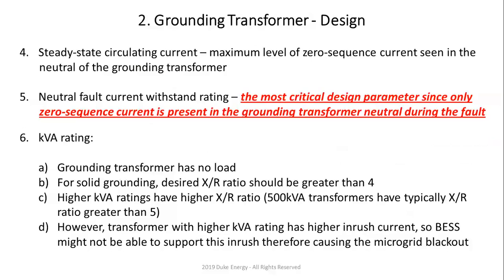So the maximum level of zero sequence current is pretty much the current flowing between the wye ground and neutral. It's going through that neutral CT. The most critical design item is the neutral current fault withstand rating, right? What happens when you have a fault?